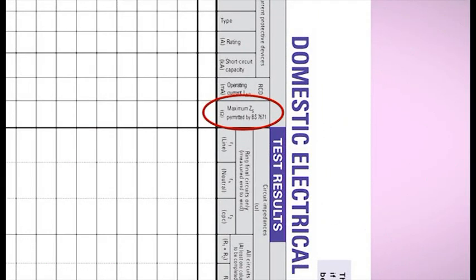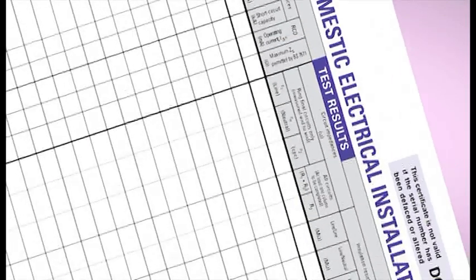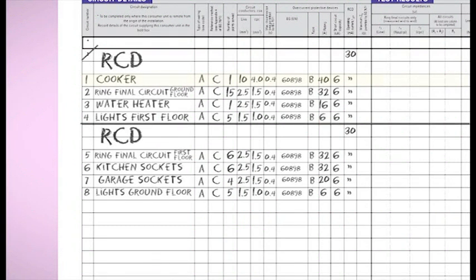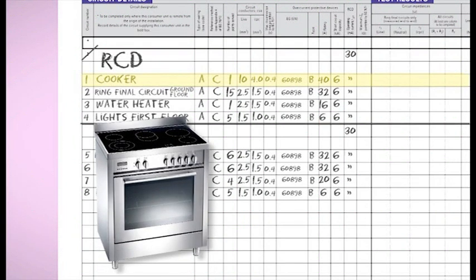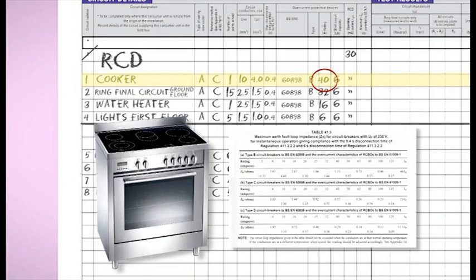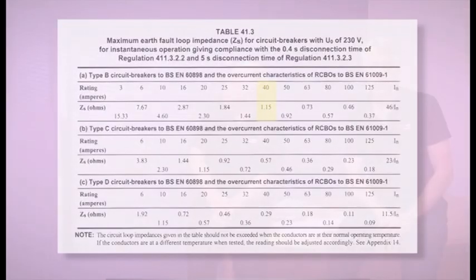Next, we have maximum ZS permitted by 7671, and this information is taken from the relevant table in Chapter 41. For example, our cooker circuit is protected by a 40 amp circuit breaker, and Table 41.3 tells us that maximum ZS is 1.15 ohms. Well, that's the circuit details covered. We now have the test results section.